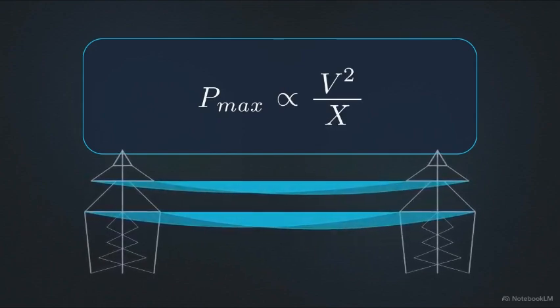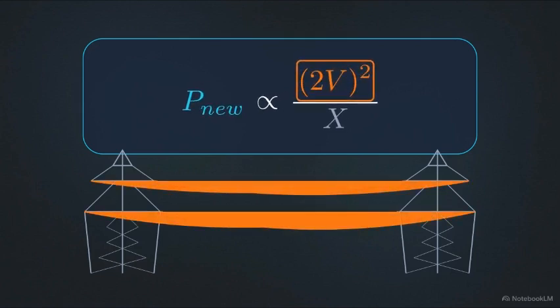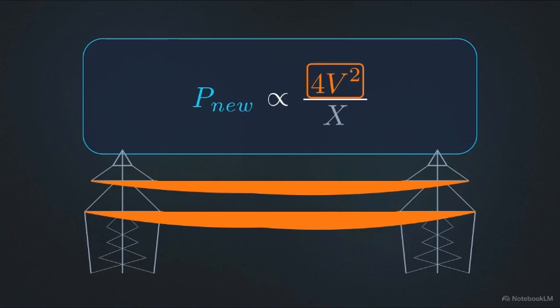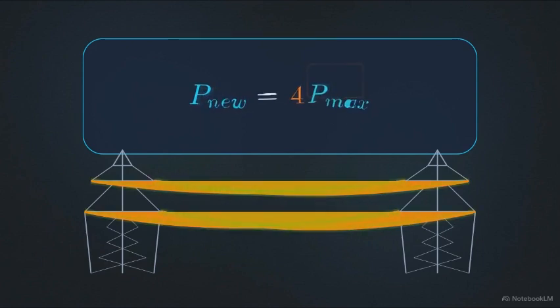This formula card illustrates the simplified proportionality rule governing the stability limit. Maximum power capacity is proportional to the square of the operating voltage divided by the line's reactance. The first method to expand capacity targets the numerator. By stepping up the grid's operating voltage, doubling it, for example, the total energy density within the line increases. Because the relationship is quadratic, doubling the voltage calculates out to a quadrupled maximum power limit.